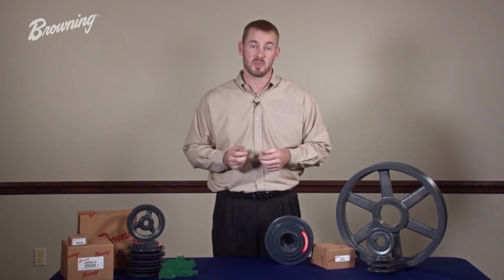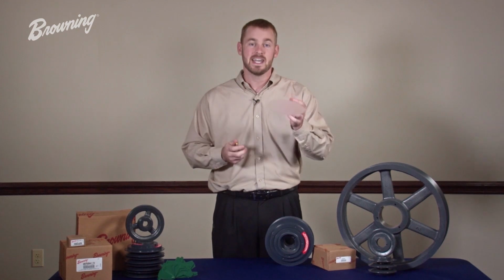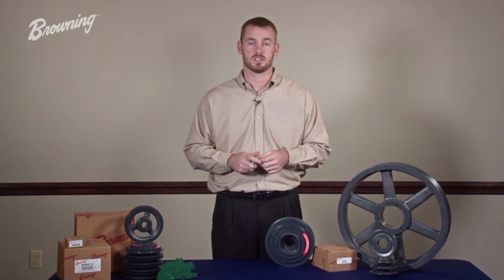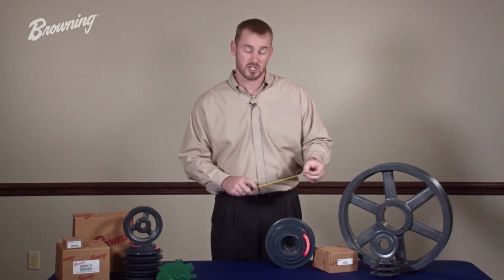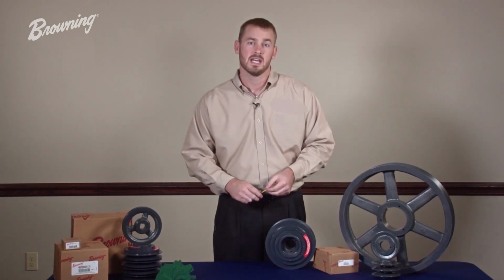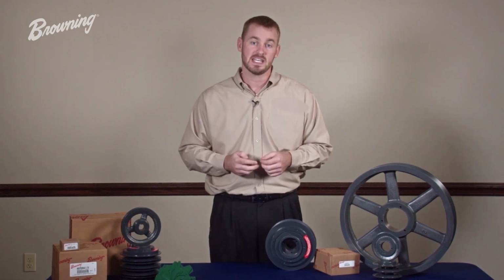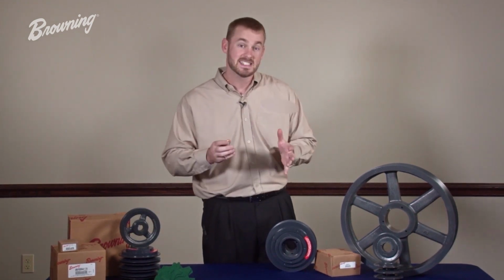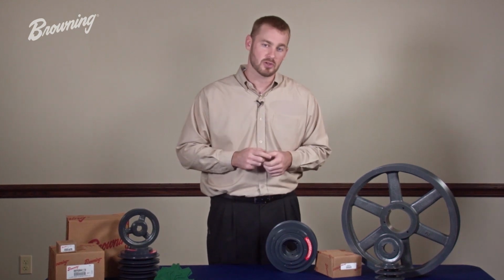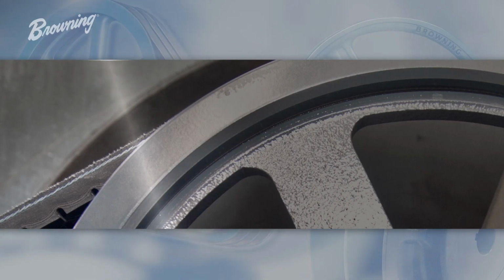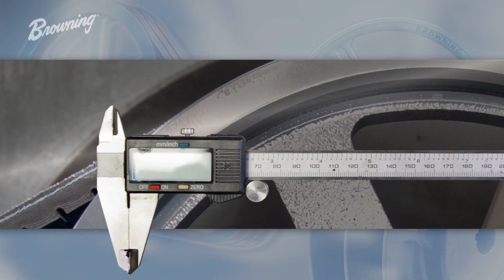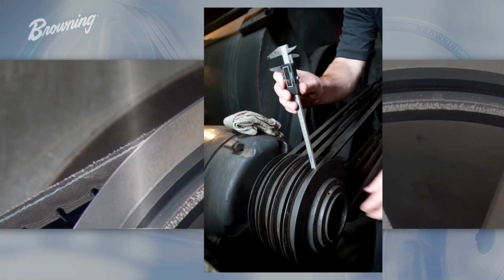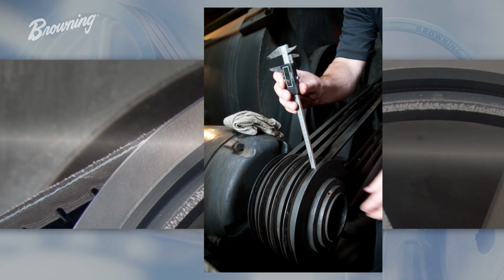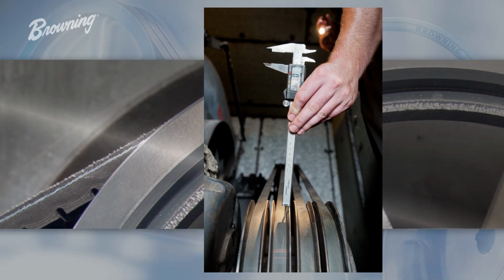If removing the belt and the sheave from the motor shaft simply is not an option, another method of determining pitch diameter can be used. First, measure the outside diameter of the sheave. Keep in mind, you may have already provided that information in the application data sheet. Second, we need you to measure the distance the belt is riding down in the groove of the sheave. This can be done with a ruler or a set of calipers. Simply place the ruler or the back side of the calipers down in the groove of the sheave so that they're resting on top of the belt. Now measure the distance to the top of the sheave and list that information in the application data sheet.